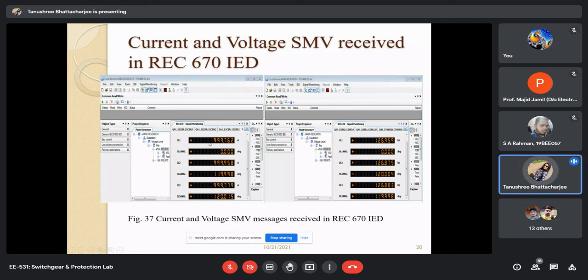You can see almost 1 kilo ampere being received. These are live real time results. Every section we are getting almost 1 kilo ampere, and voltage is around 126 kV. Why 126 kV? Again 220 divided by √3, which is around 127.